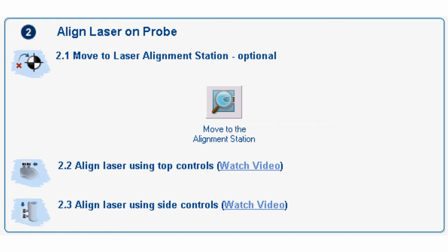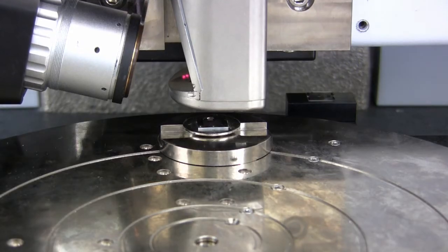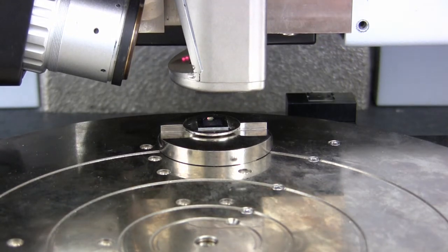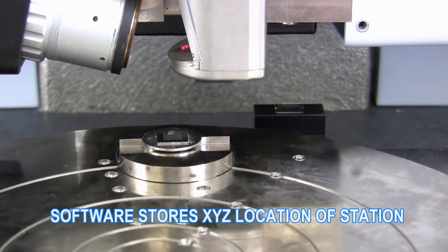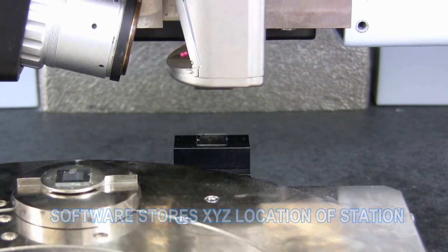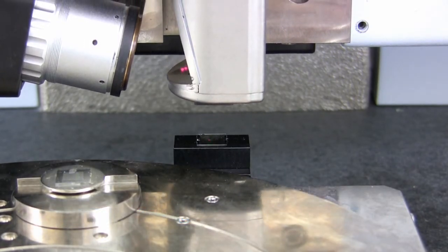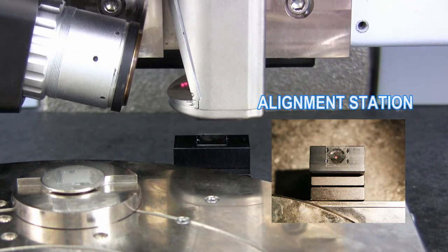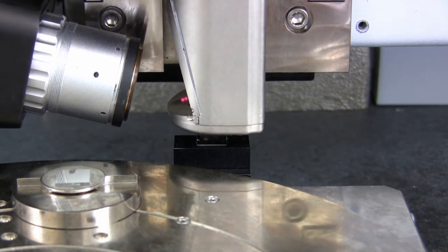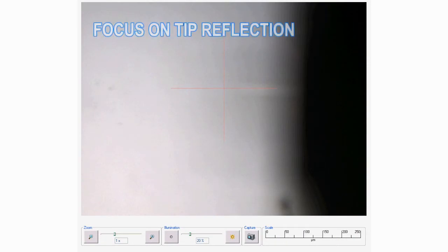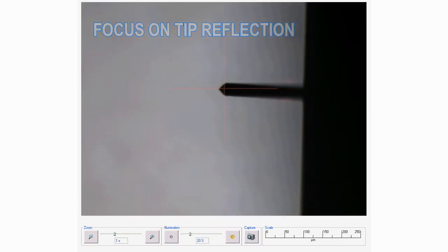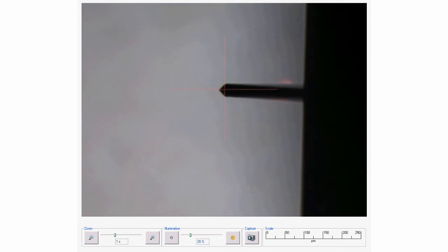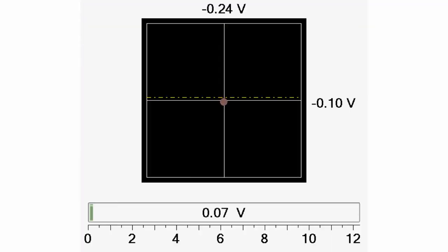Use the software command Move to Alignment Station in the Setup screen menu to translate the stage forward. The station is located near the back of the sample chuck. This allows the probe to be placed above a reflective surface so that the image of the laser spot and the mirror image of the cantilever can be viewed at the same time. Lower the focus to see the tip reflection image, and then move the alignment knobs until you see the laser spot visible near the end of the cantilever. As the laser moves over the cantilever arm, the sum signal should start to increase.